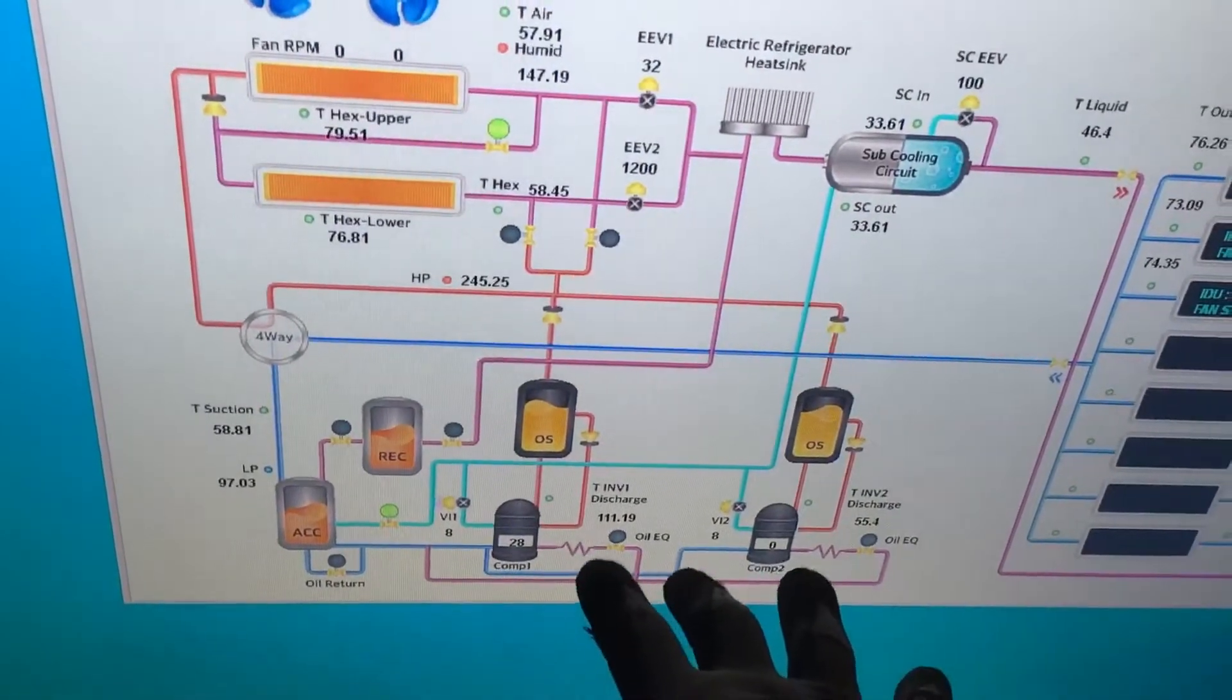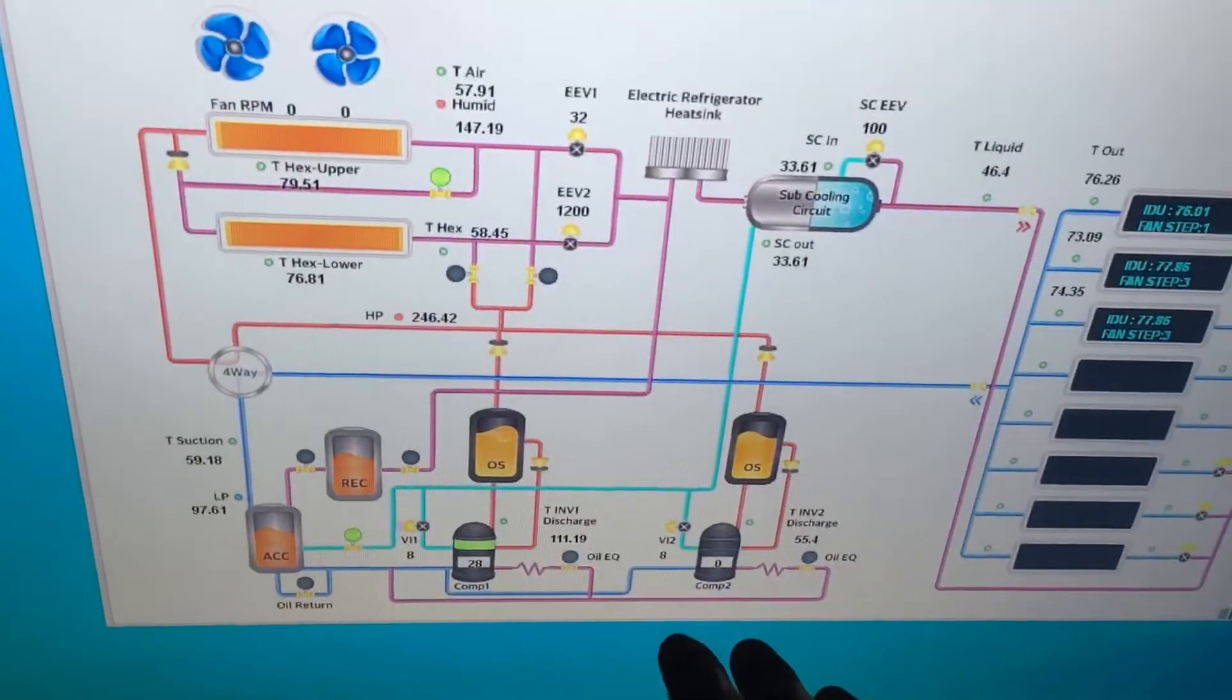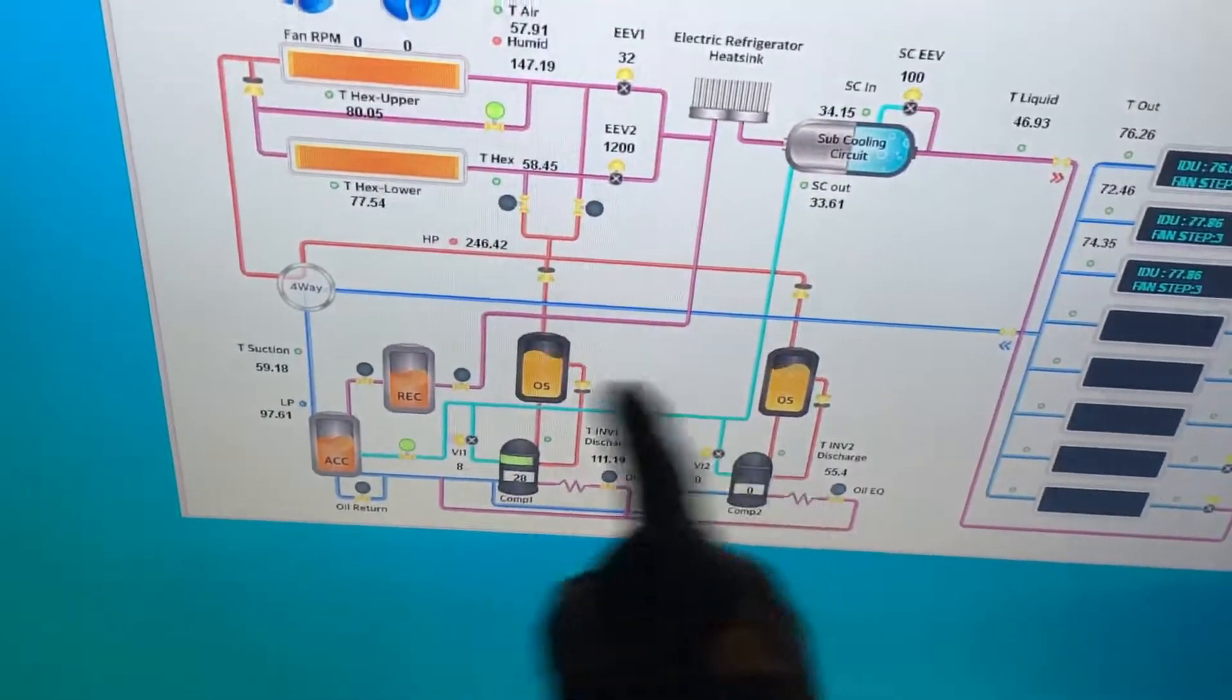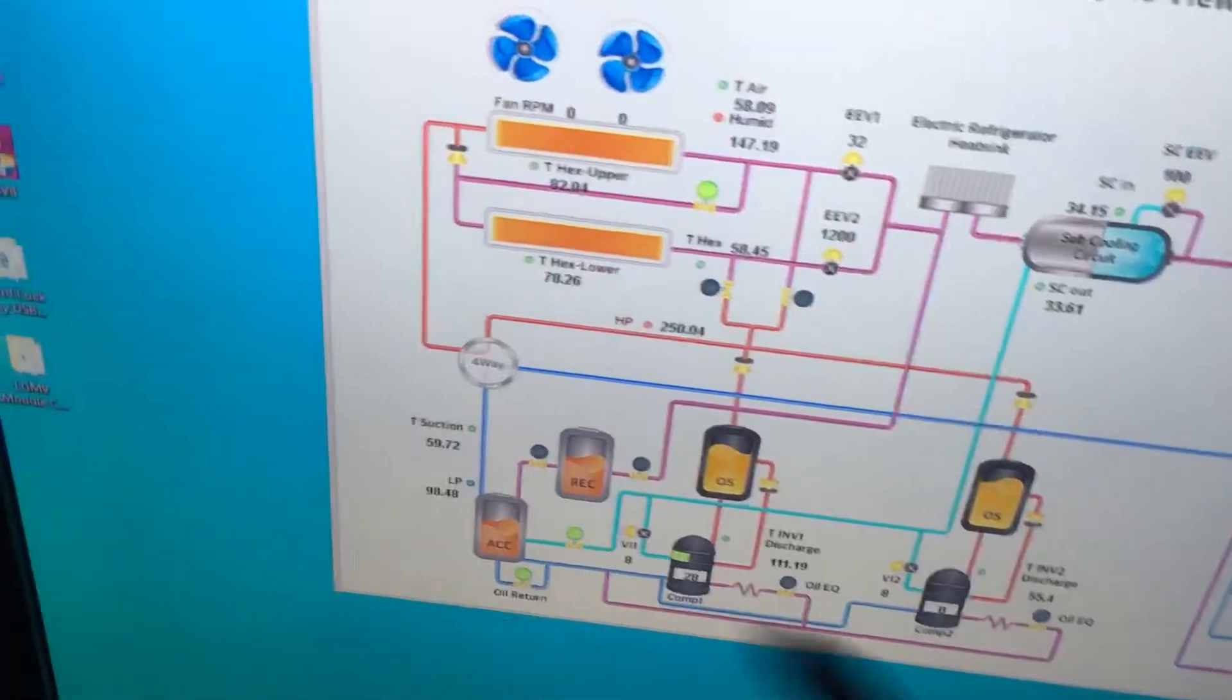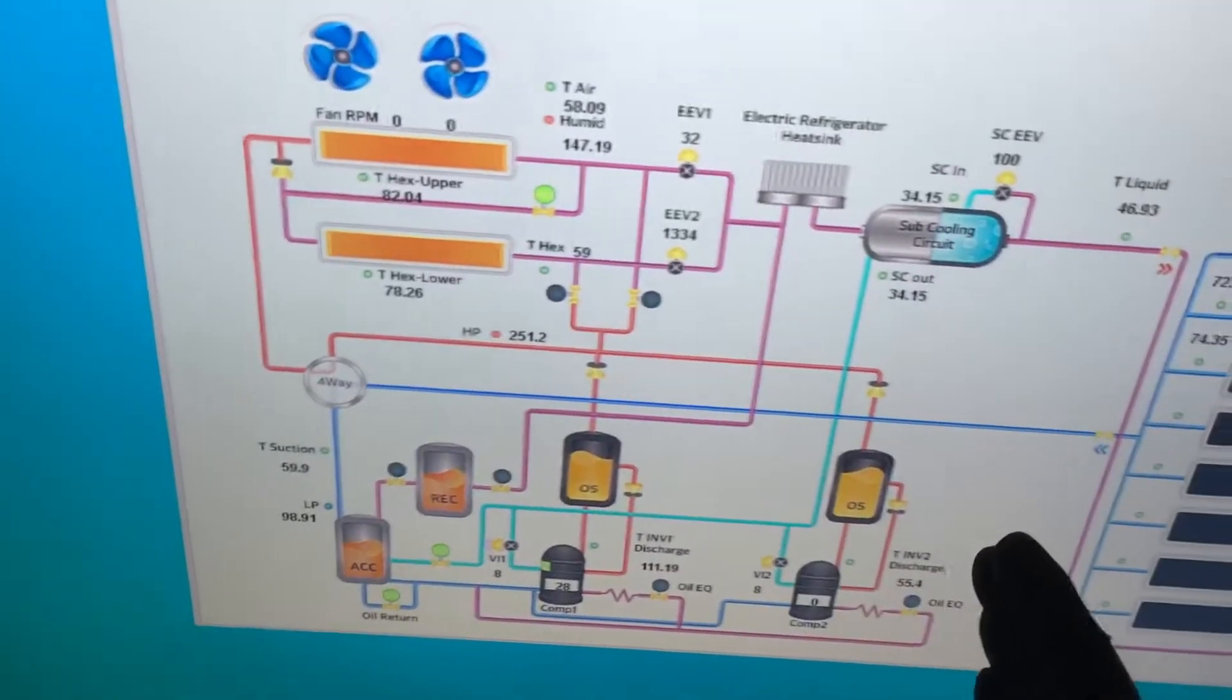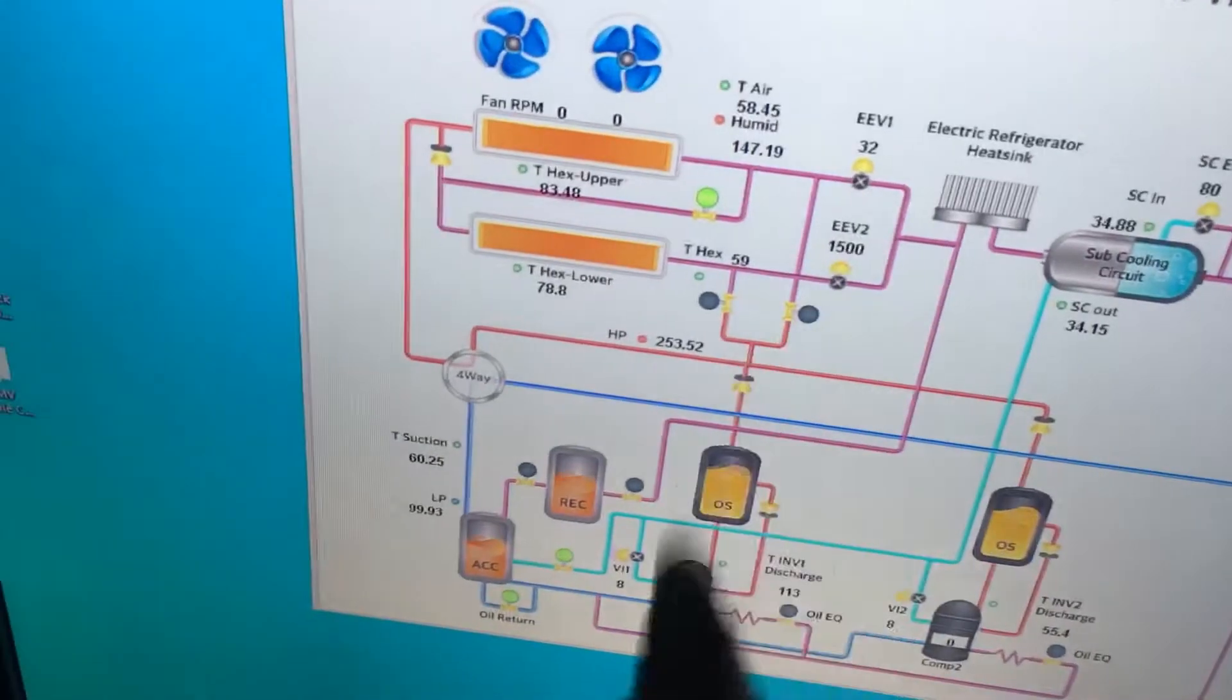It never stresses any one compressor out. What it does is it counts the hours on every compressor and on every system. When we have this other system up there, it'll literally rotate compressors and systems to keep the equal amount of run time on all the compressors.